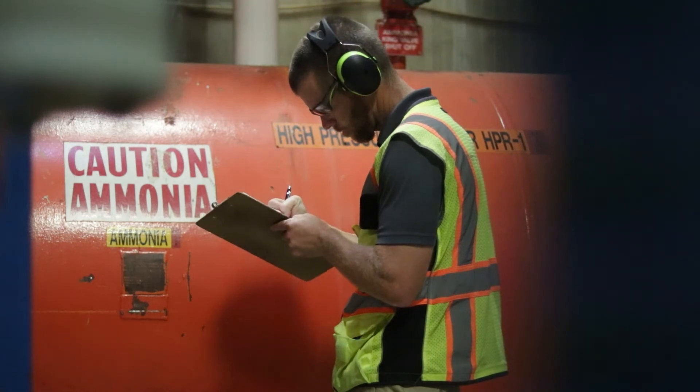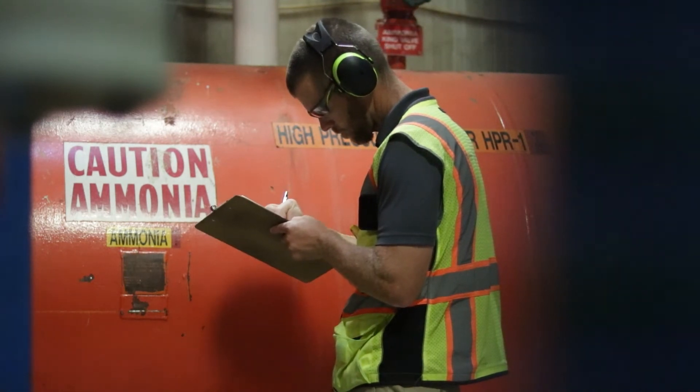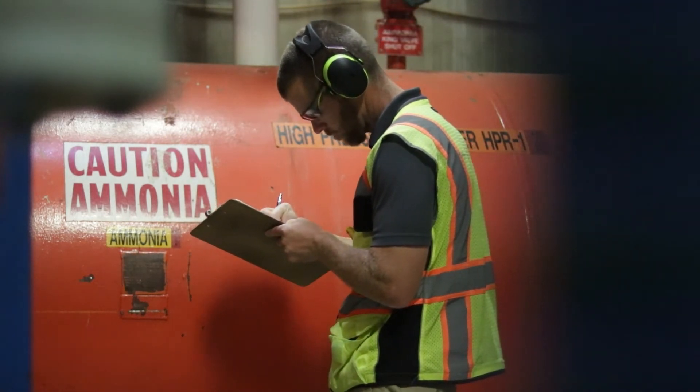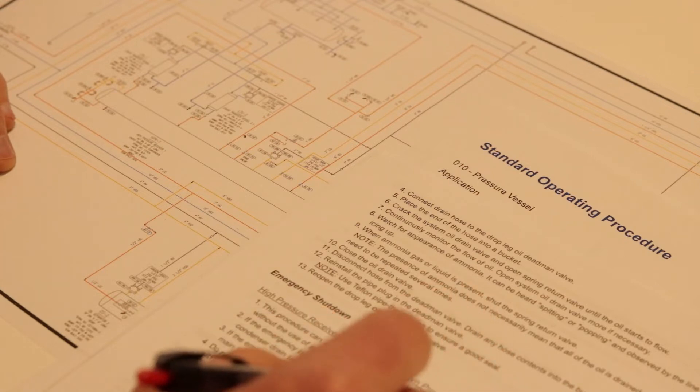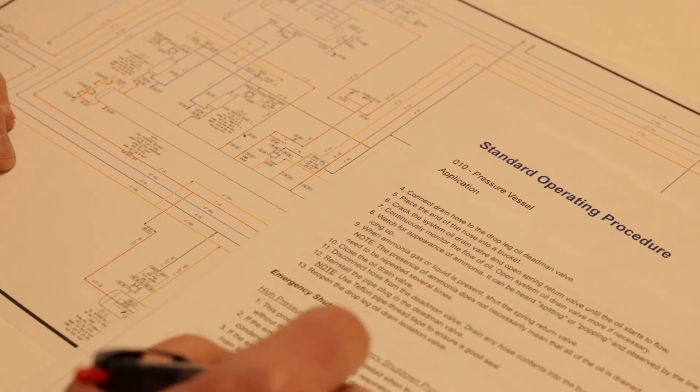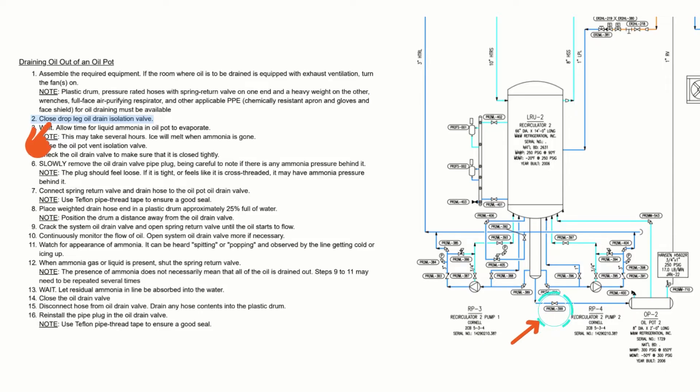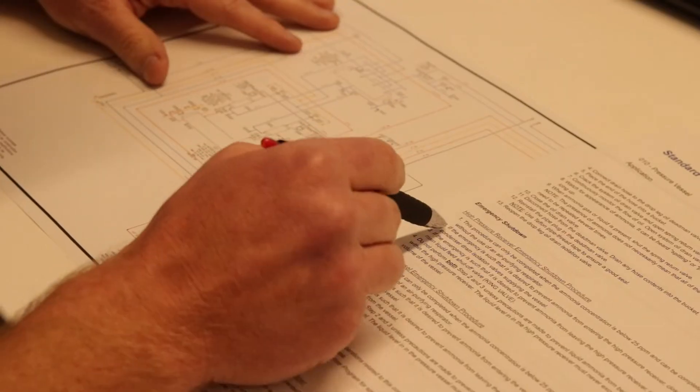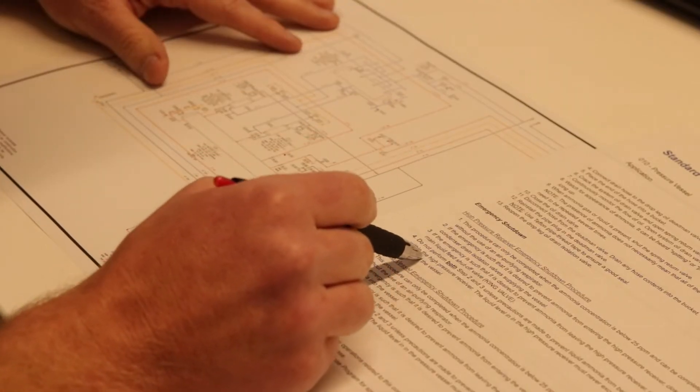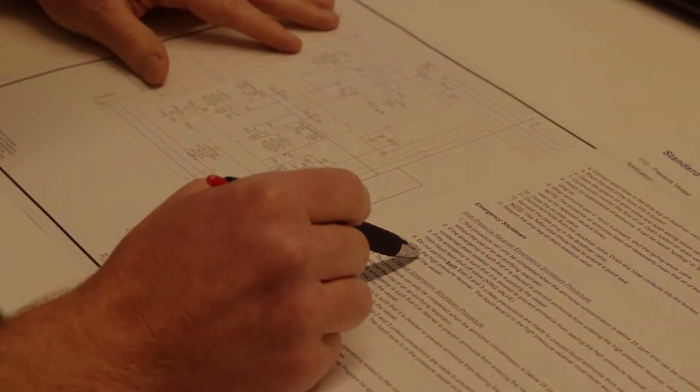When an SOP specifies that a certain valve be manipulated, the P&ID must depict that valve. To ensure that SOPs and P&IDs are consistent, we suggest reviewing SOPs side-by-side with the P&IDs. Where actions are called out in an SOP, an operator should be able to identify the components referenced on the P&ID.